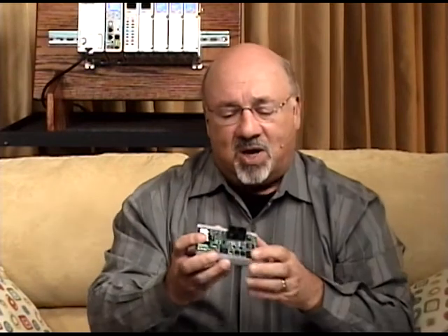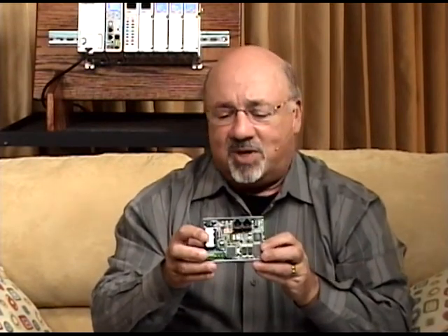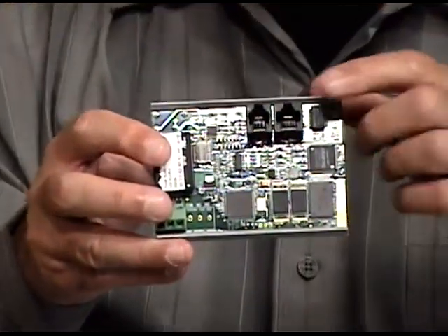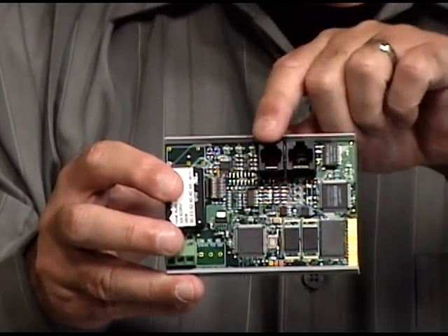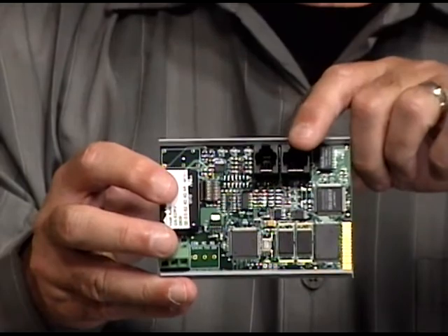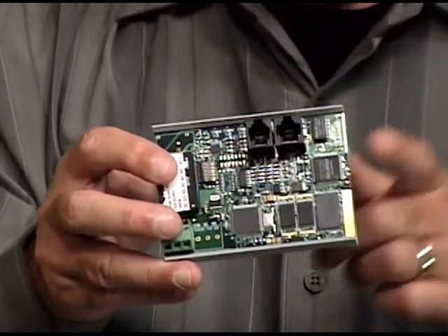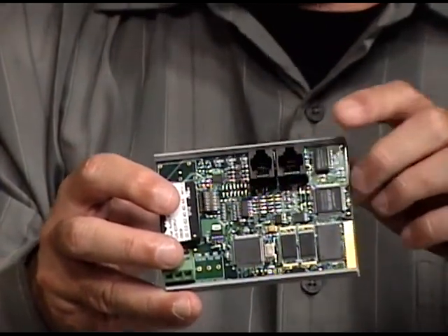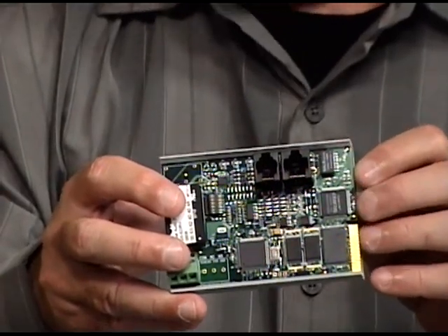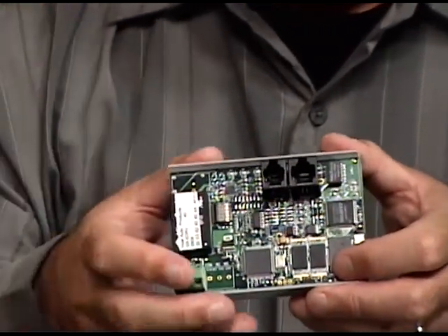One of our E-drives that we can connect up to the GS drive or a Durapulse drive. The Productivity 3000 also has the ability to run an Ethernet cable from the one plug here. This is actually RS485 that goes to the drive, but we can hang up to, I think it's 64 GS type drives off of these E-drive interface cards, and auto configure them directly from the Productivity 3000 software. So just another one of our Ethernet abilities and features, and I think that concludes everything I had to say at this point.